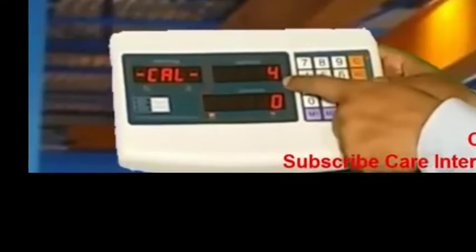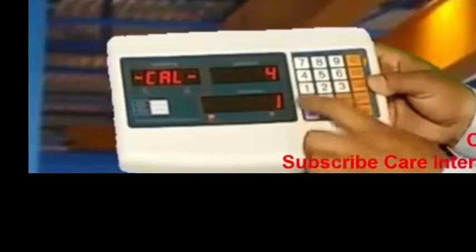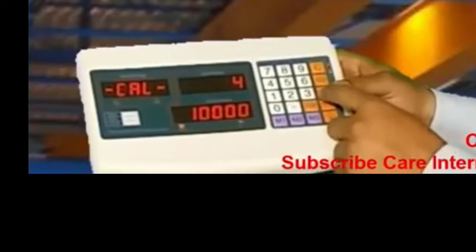We write full capacity 100kg. After the point, we write two zeros. After that, press tare button which shows CAL 4 on the screen.